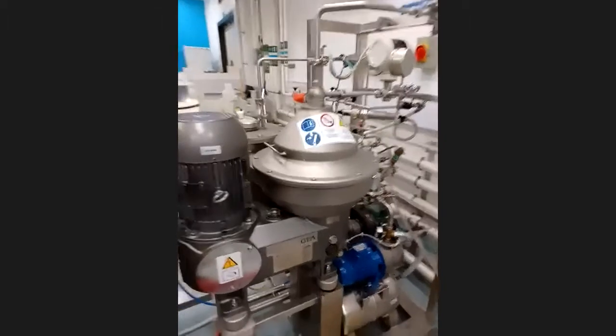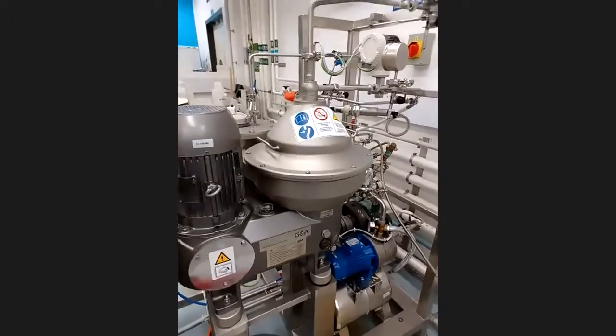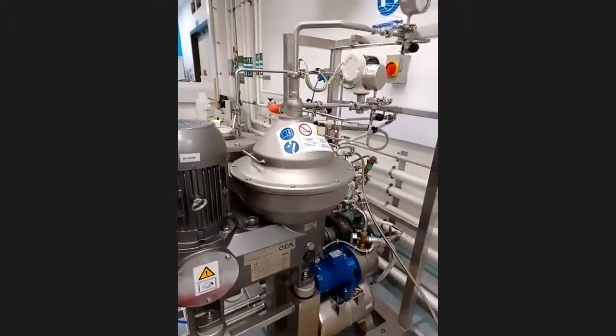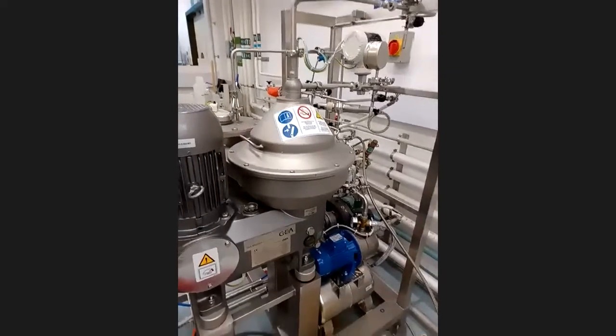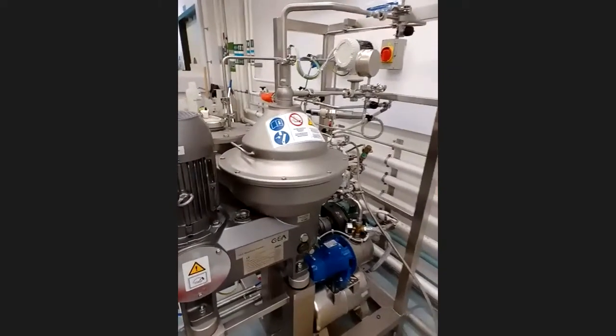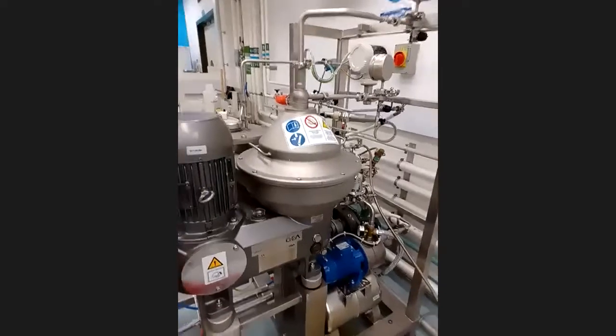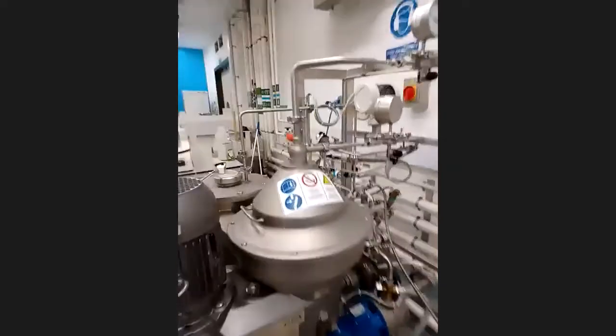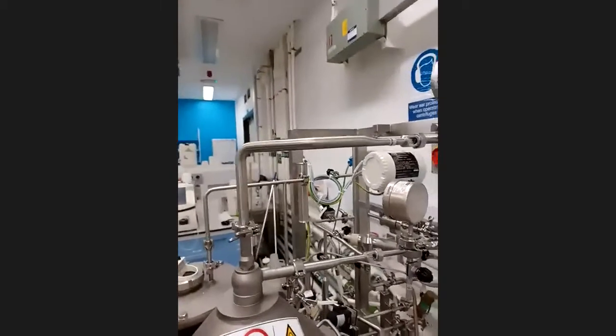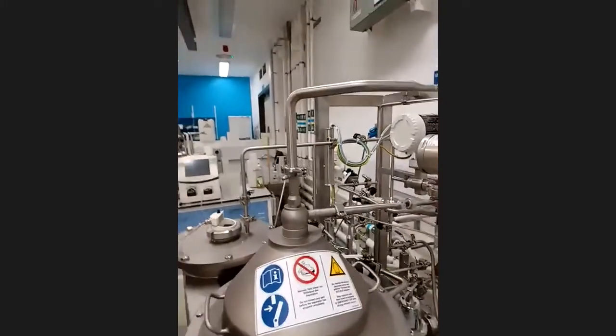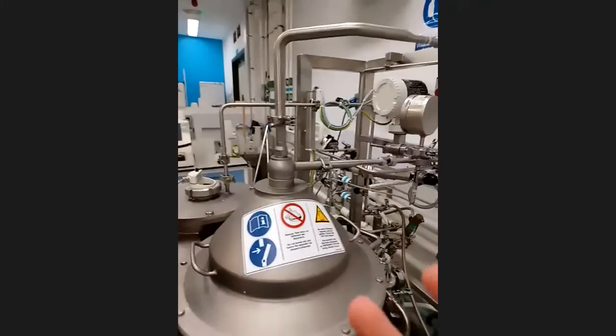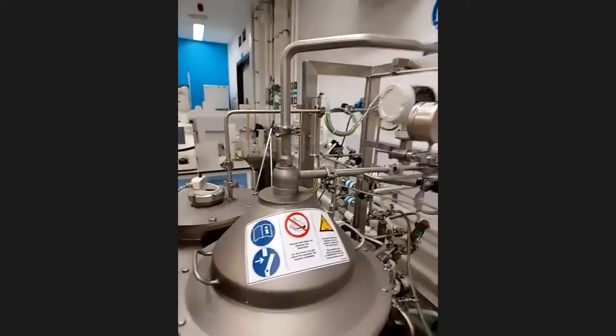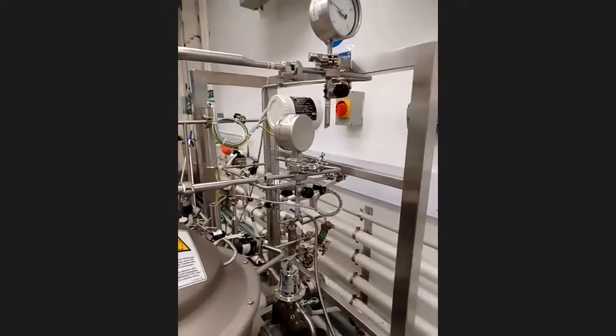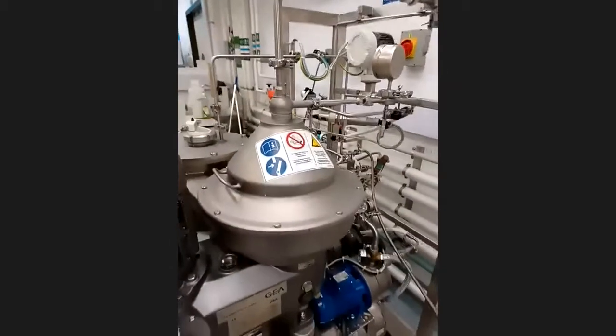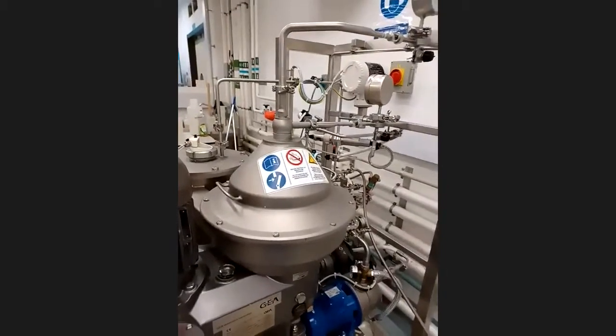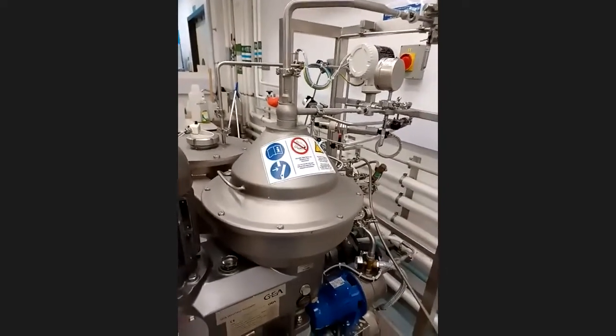So we flow liquid in because the bowl is rotating at high speed. This one here rotates at about 13,500 RPM. The solids, being more dense, will deposit themselves inside the bowl and the clarified liquid comes out. On this machine, the tube coming from the top is where the liquid comes in. It then goes through the centrifuge, solids deposit themselves inside the bowl, and a clarified liquid is collected, okay? With a machine this size, a 1 litre bowl, we could do about 200 litres an hour.